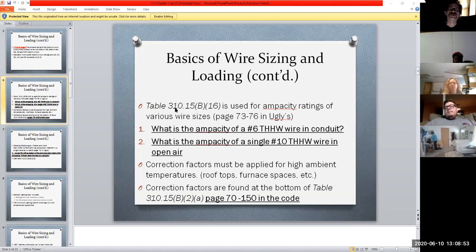So then there's a table that's used for ampacity ratings. It's in the Ugly's book, and it lists the current carrying capabilities of your different wire sizes. Like how much current can number 14 hold, how much can number 12, number 10, number 8, and so on. It's also based on temperature. So we look at the 75 degrees Celsius column, and we go down the line and look at that. And we have to look at the insulation involved with our wiring.